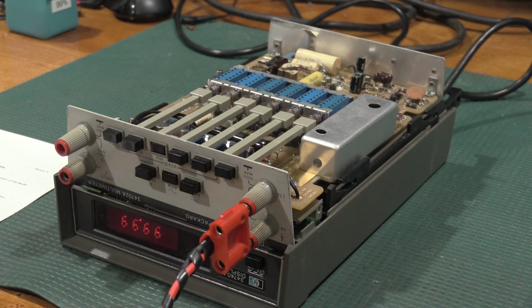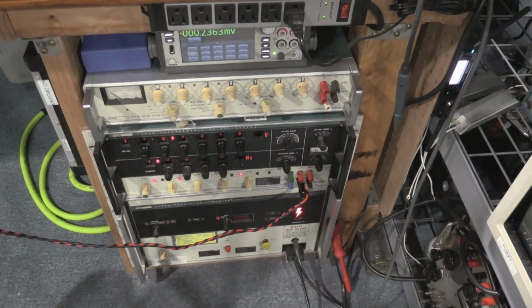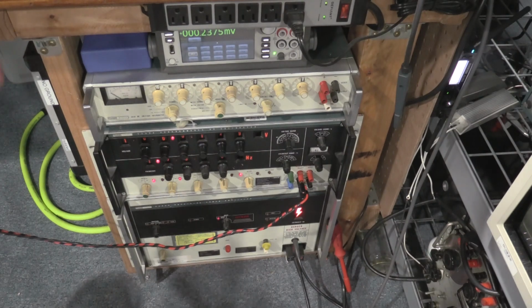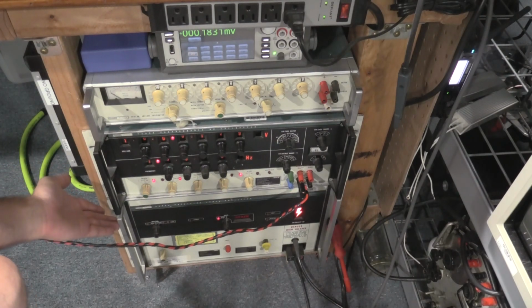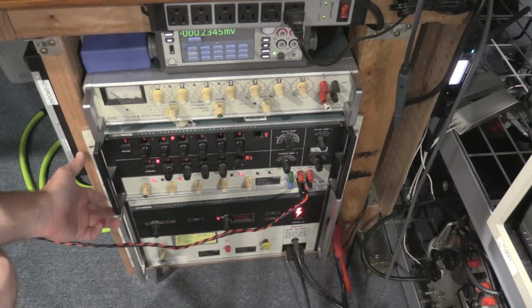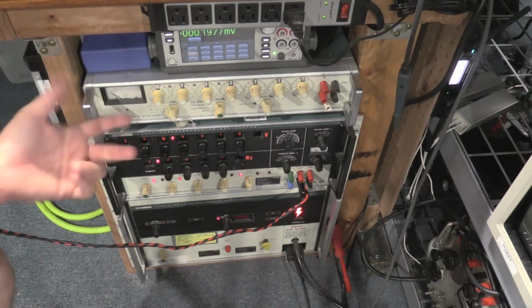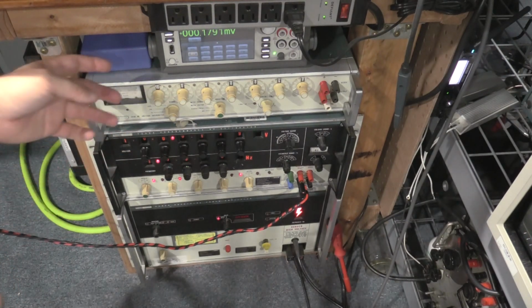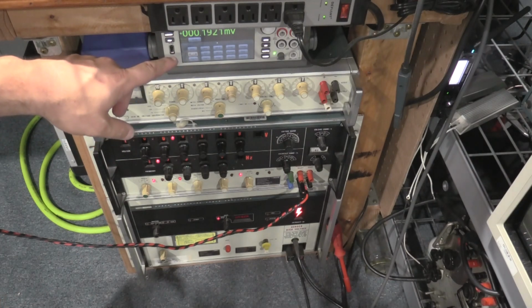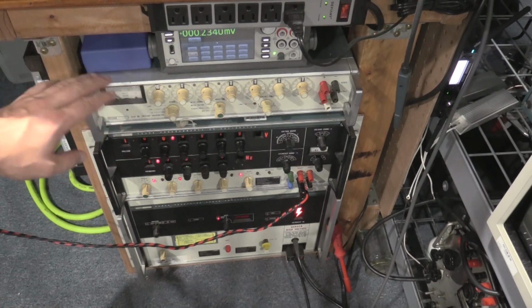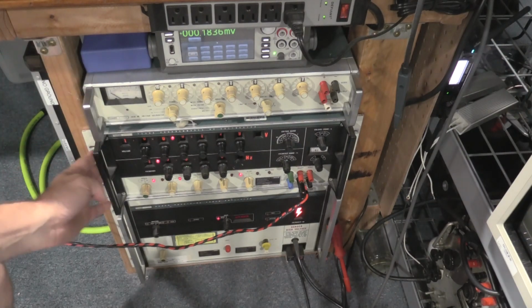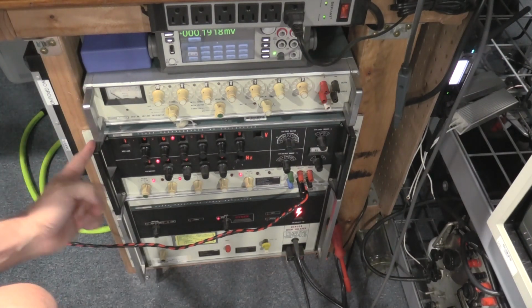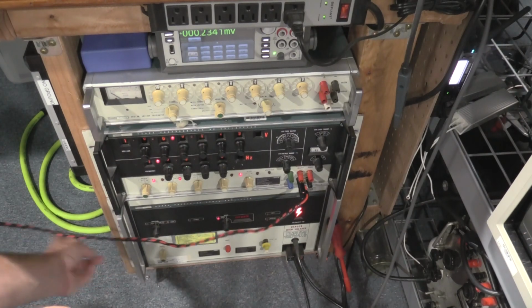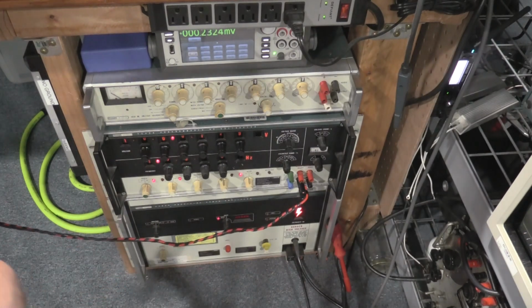All right, I got to get the big guy out now, so we got to do the 1000 volt AC range. For those that are new to the channel, just finding it for the first time, these are the signal sources that I use for doing these alignments: DC, AC, and high voltage AC. This guy puts out a lot of heat. Actually, he puts out enough heat where ACAL on this one got cranky, and it wants me to run ACAL on the 7510. So this is a 7.5-digit DMM, which I'm using as a transfer standard for the DC source. The AC source up to 100 volts. This and this are coupled together, and I have a 1000 volt AC source down here.